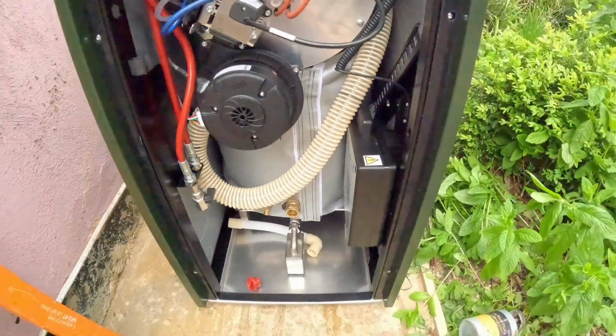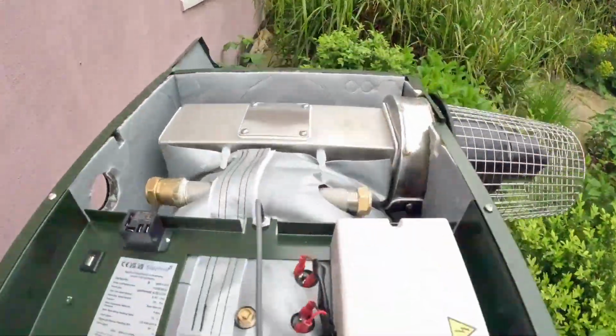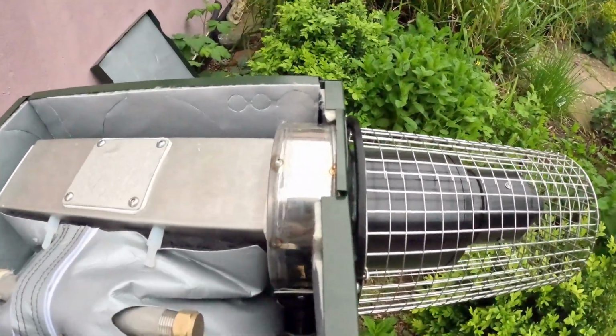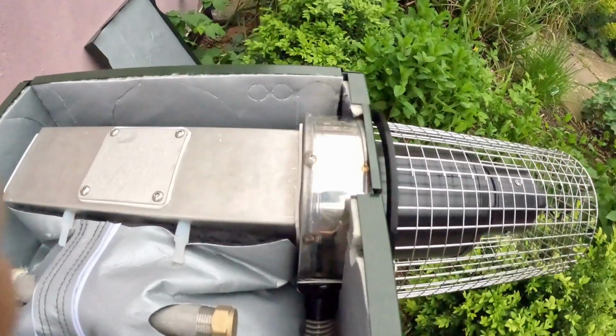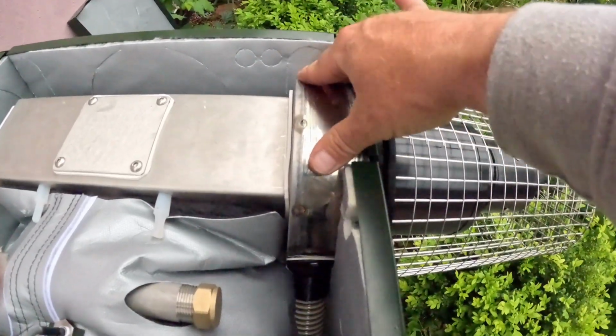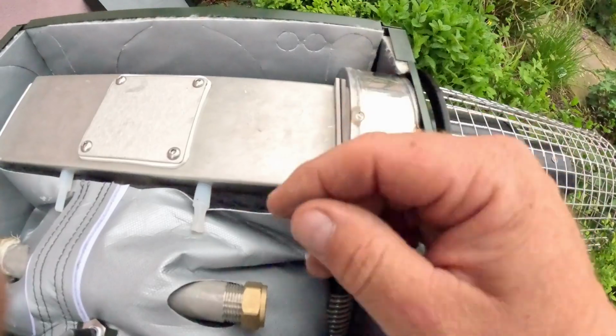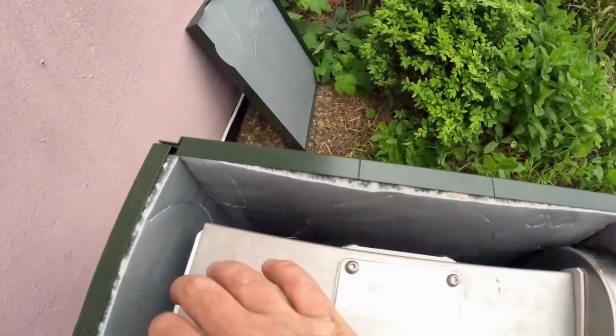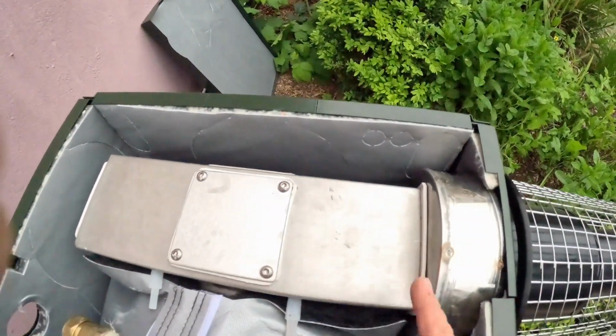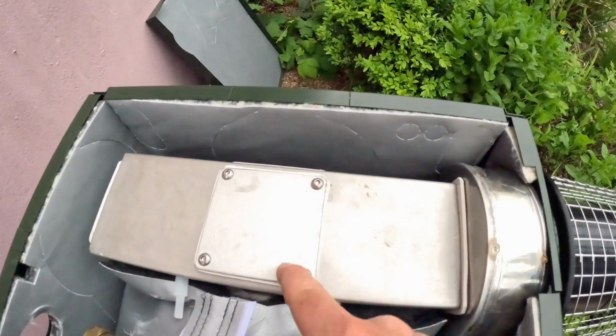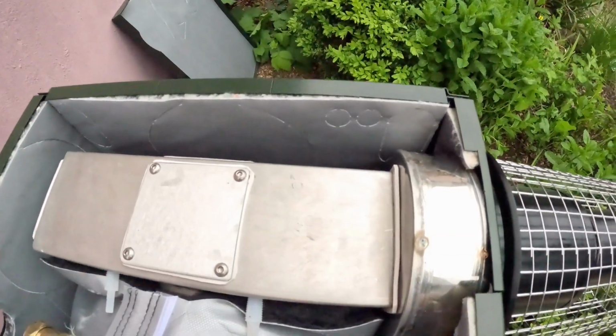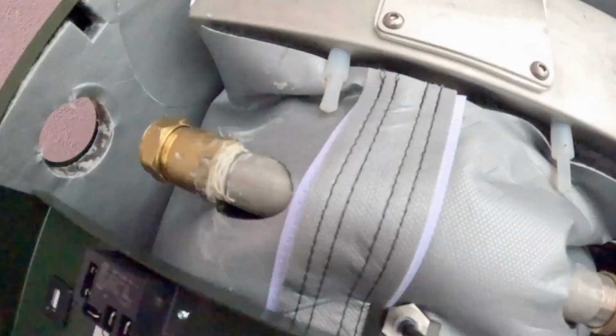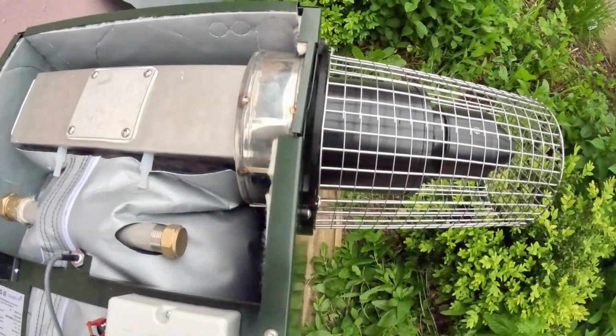The flue's a bit tricky. I don't know if you have to take the side off, but we had to take it off to get in. What you have to do is put this air intake box on, so you get a choice of back or side. You have to take the gasket off here with a blanking plate like that, and put this on, which is really tight. Again though, they've been really clever - they've notched all the insulation out to take that, you might be able to see it better there, but it's still intact down the bottom.